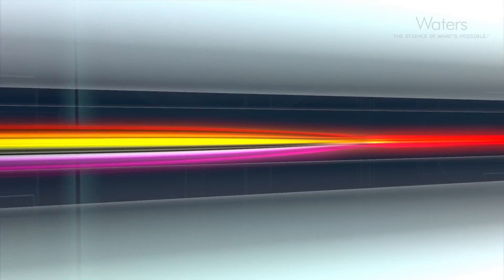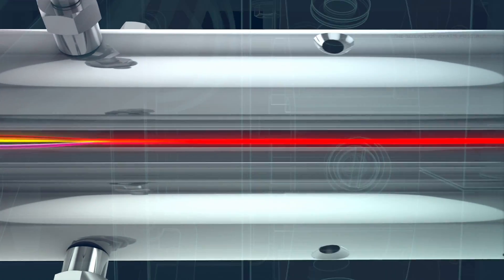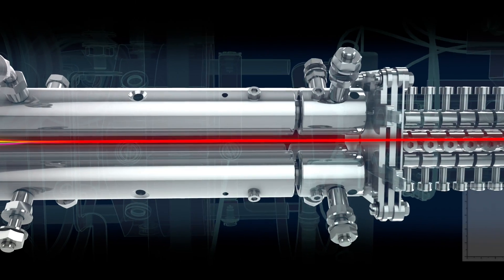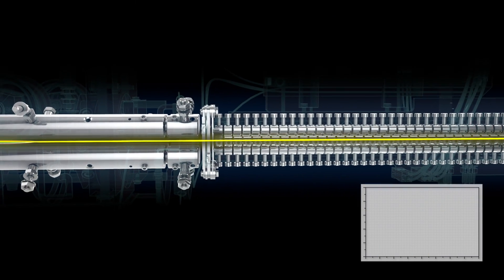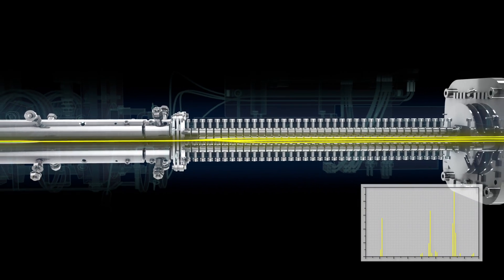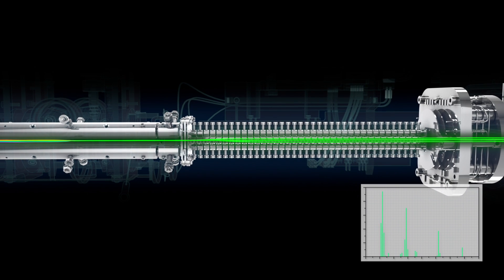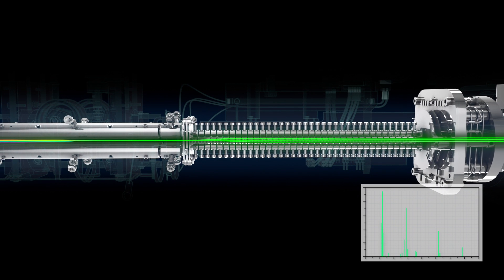Using this technique, we're able to generate up to 2,000 individual and very clean MSMS spectra per second for the duration of the chromatographic run. In essence, we get a very complete survey of the sample. After peak detection in the time-of-flight spectrum and quadrupole scan dimensions, we're able to say very precisely which fragments are coming from which precursor ions.